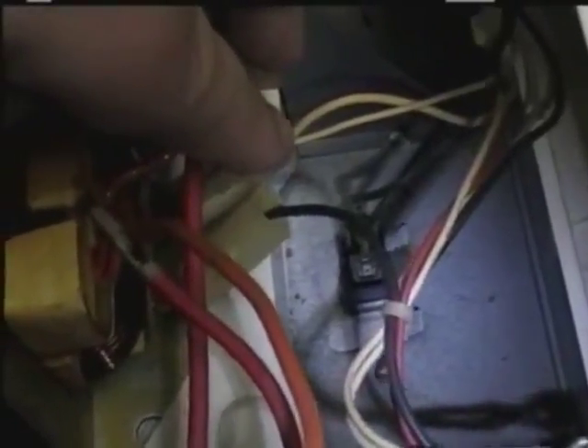First thing you can check is to see if the transformer is getting any power. You do this by, get my test leads out of the way. You'll see these two black cables. One's black, one's white. The black one is the hot one. This is the neutral. What you want to do is unhook them like this. Take the other one like that.